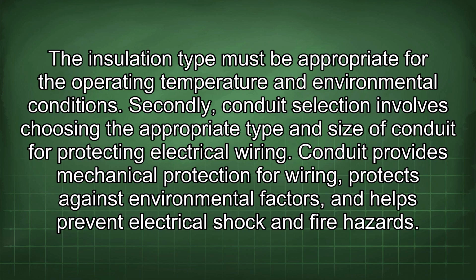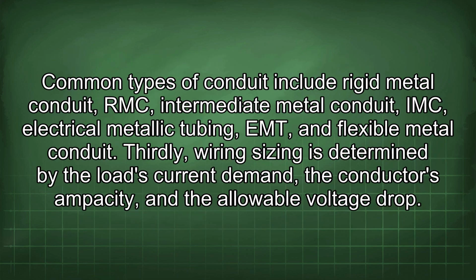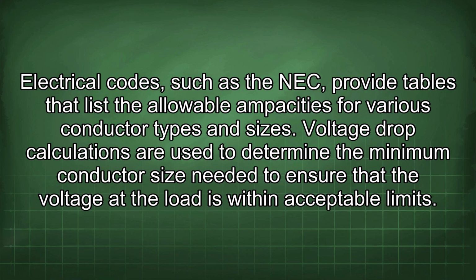Secondly, conduit selection involves choosing the appropriate type and size of conduit for protecting electrical wiring. Conduit provides mechanical protection for wiring, protects against environmental factors, and helps prevent electrical shock and fire hazards. Common types of conduit include rigid metal conduit (RMC), intermediate metal conduit (IMC), electrical metallic tubing (EMT), and flexible metal conduit. Thirdly, wiring sizing is determined by the load's current demand, the conductor's ampacity, and the allowable voltage drop. Electrical codes, such as the NEC, provide tables that list the allowable ampacities for various conductor types and sizes.